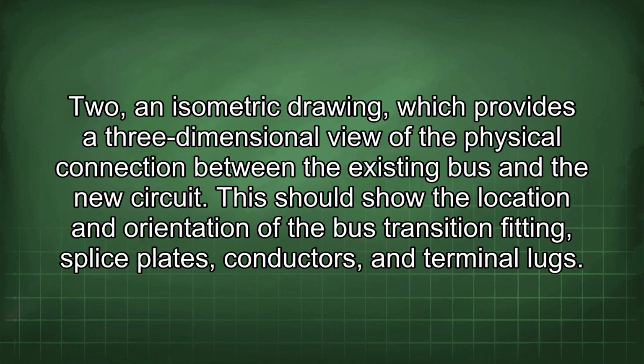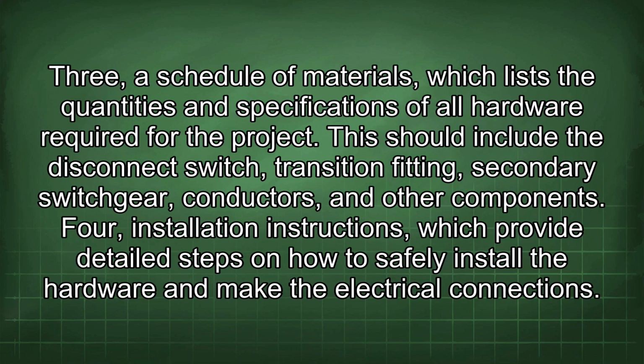2. An isometric drawing, which provides a three-dimensional view of the physical connection between the existing bus and the new circuit. This should show the location and orientation of the bus transition fitting, splice plates, conductors, and terminal lugs. 3. A schedule of materials, which lists the quantities and specifications of all hardware required for the project. This should include the disconnect switch, transition fitting, secondary switchgear, conductors, and other components.